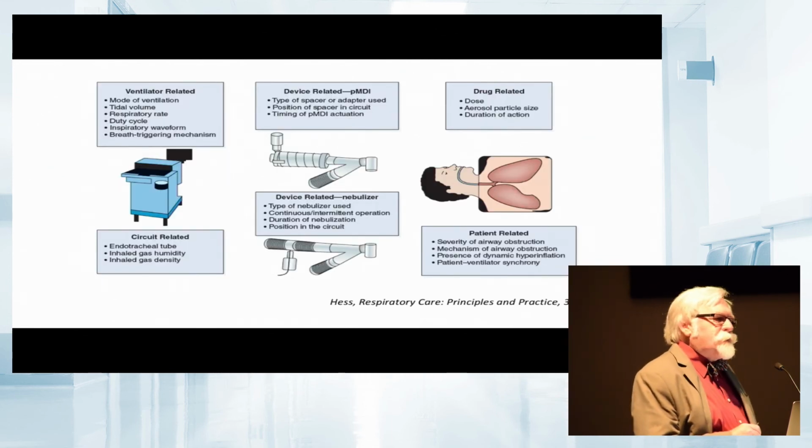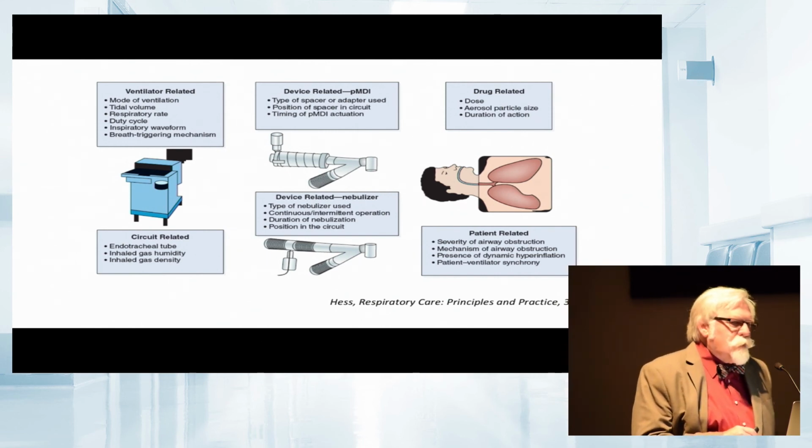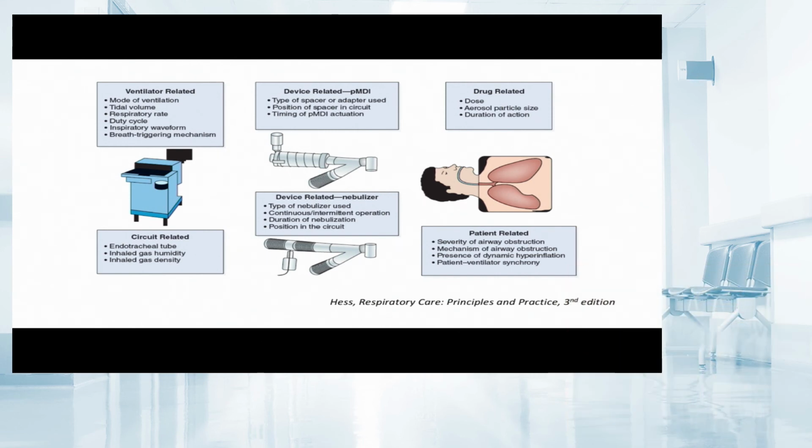There are a number of factors that affect aerosol delivery during mechanical ventilation. These relate to the ventilator and how the ventilator is set. These relate to the ventilator circuit, things such as the endotracheal tube and whether or not we humidify the inspired gas and the density of the gas. There are issues related to the inhaler, if we use an inhaler to deliver the drug. There are issues related to the nebulizer. We'll talk about these in more detail over the next several minutes. There can be issues related to the drug formulation, and then there can be issues related to the patient.